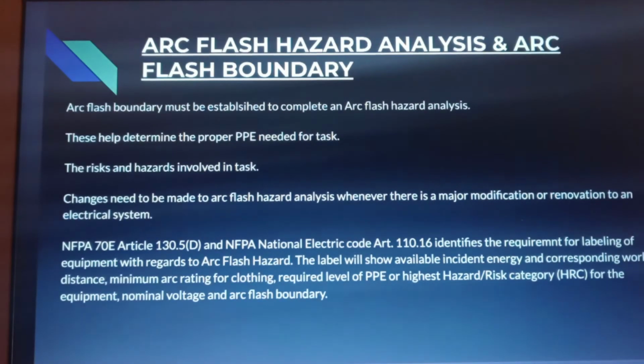All right, and now we're going to get into arc flash hazard analysis and arc flash boundaries. The arc flash boundaries must be established to complete an arc flash hazard analysis. These help determine the proper PPE needed for a task, and the risk and hazards involved in the task. Changes need to be made to the arc flash hazard analysis whenever there is a major modification or renovation to an electrical system.